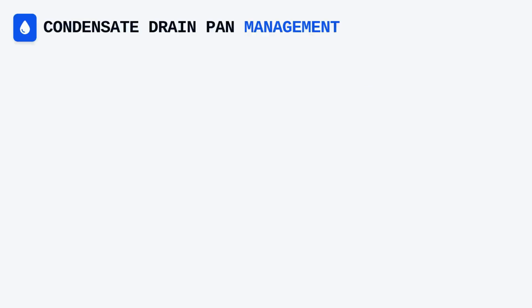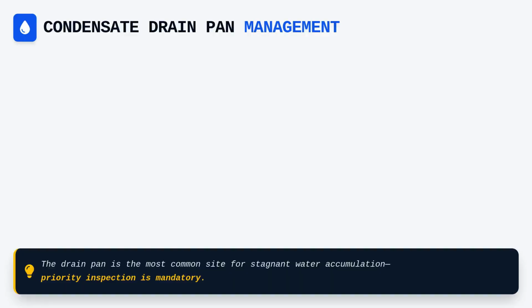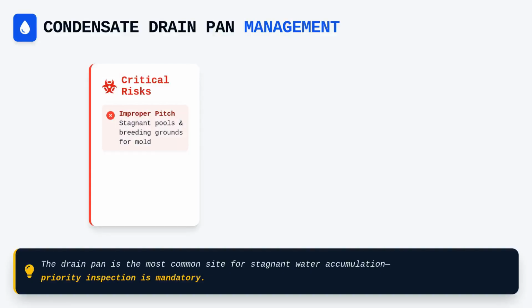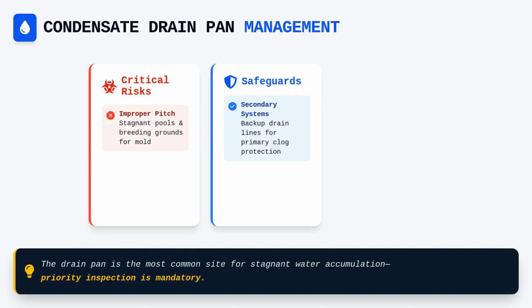Management of the condensate drain pan is equally critical, as this is the most common site for stagnant water accumulation within an AHU. A drain pan that is improperly pitched will never fully evacuate fluids, leaving behind pools of moisture that serve as a breeding ground for bacteria and mold. Beyond the basic drainage, we have to look for the presence and functionality of secondary drain systems and float switches designed to prevent water damage during primary drain line clogs.